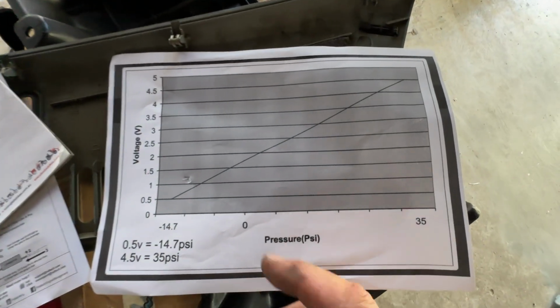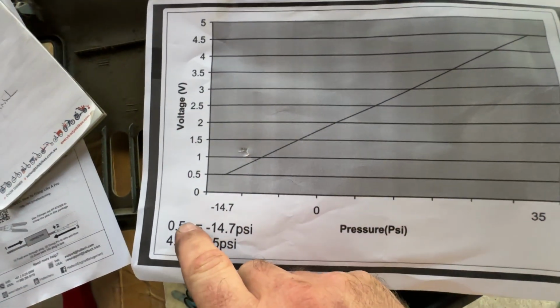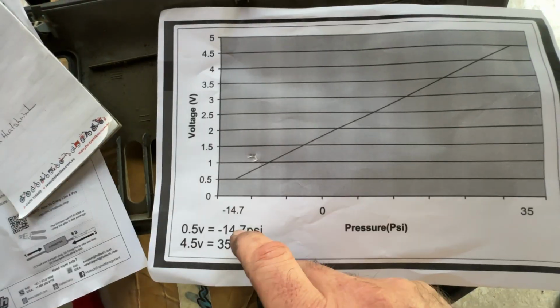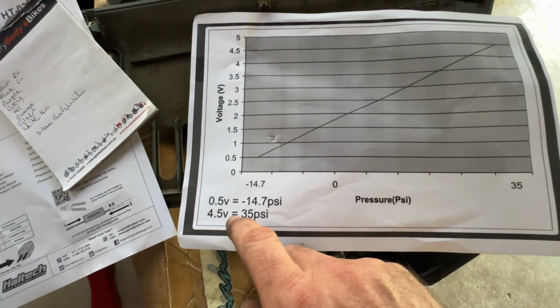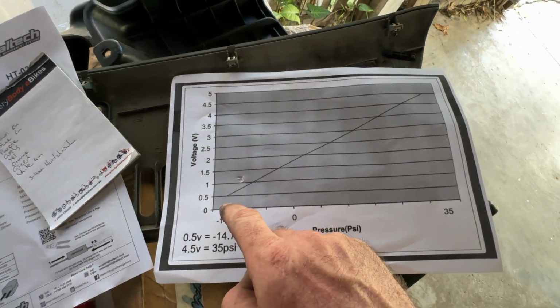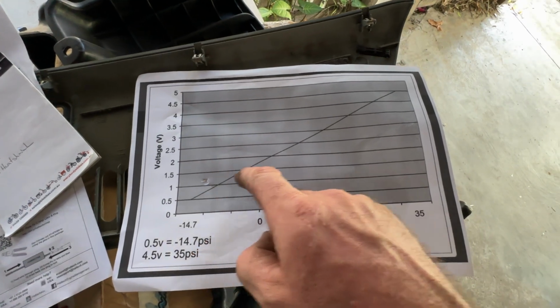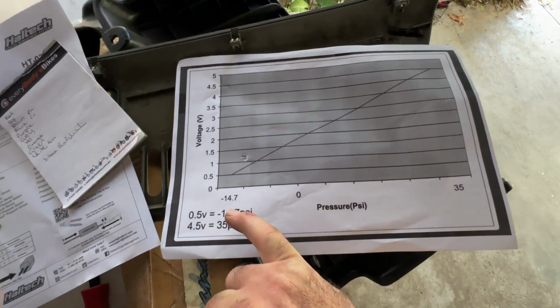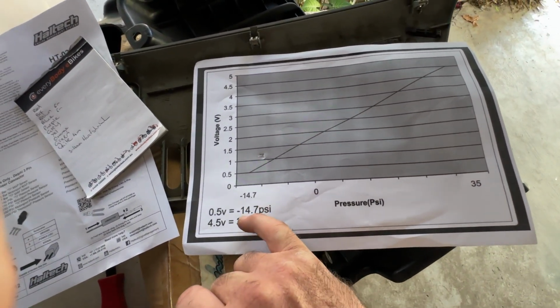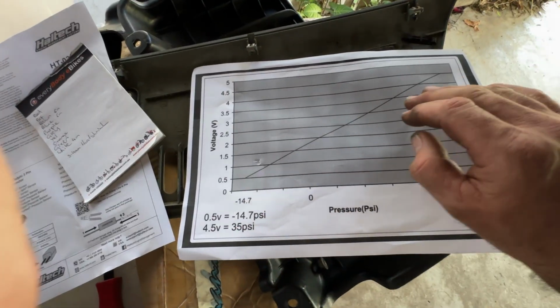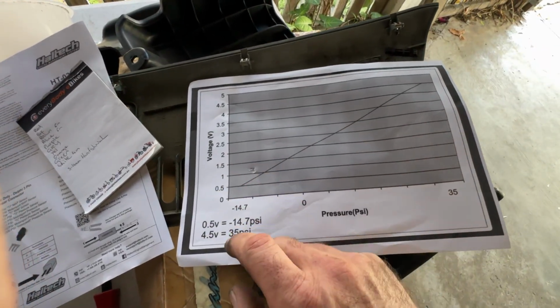Here's the calibration here, it's linear. So 0.5 volts equals negative 14.7, 4.5 equals 35 psi. Linear, so it's straight, as opposed to being curved. So there's different cal tables, some are for linear, some are for a curved one. So you need to work out what cal table to use.